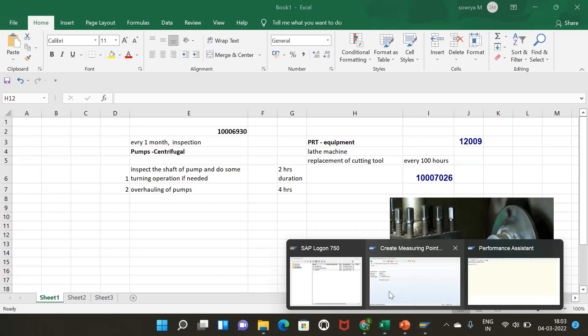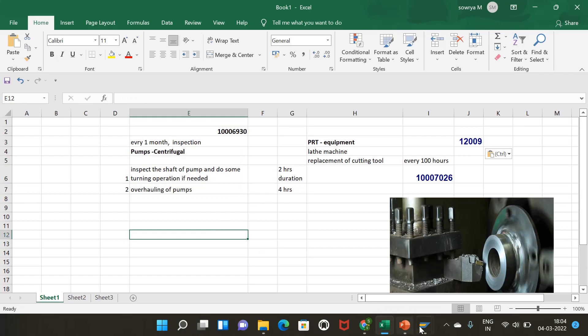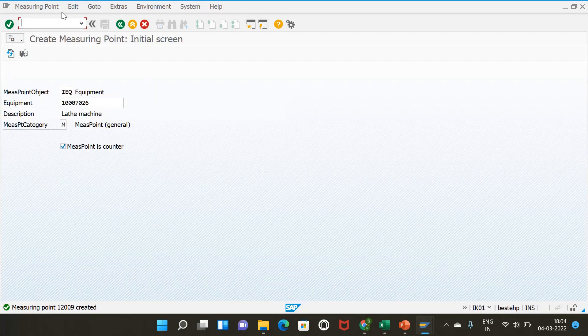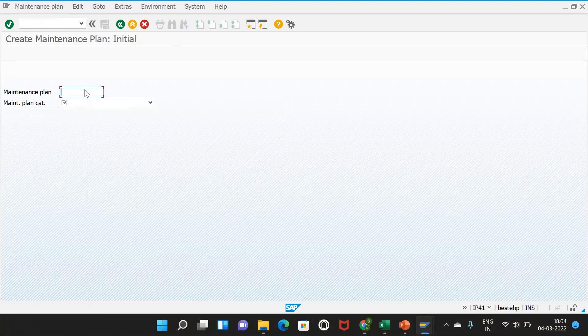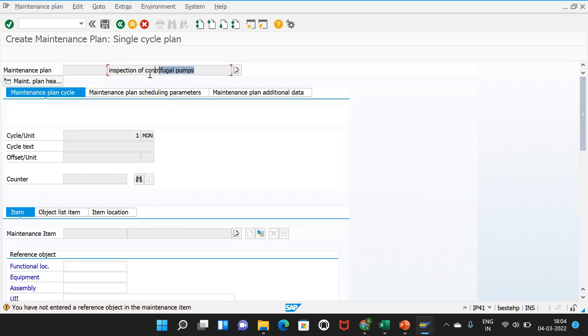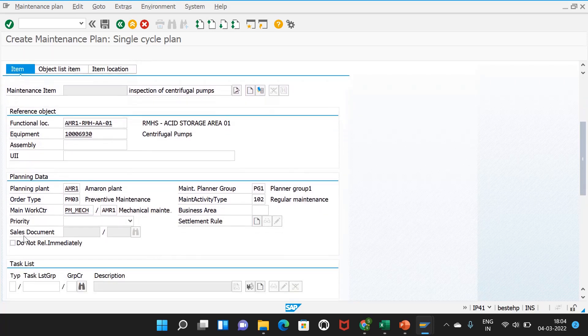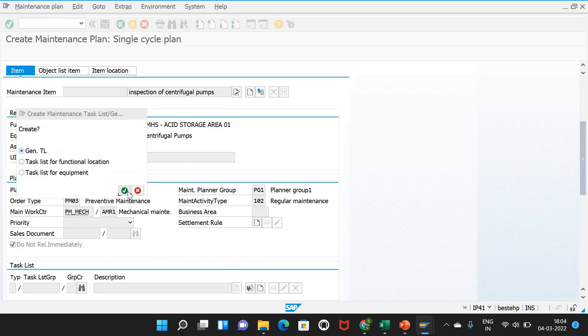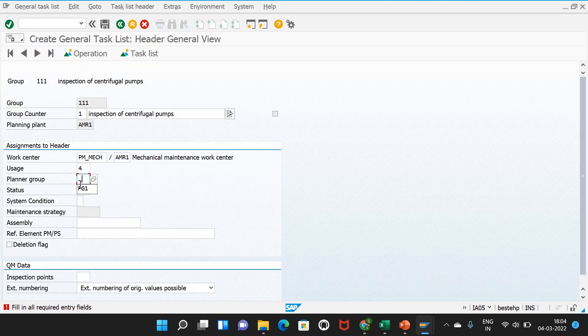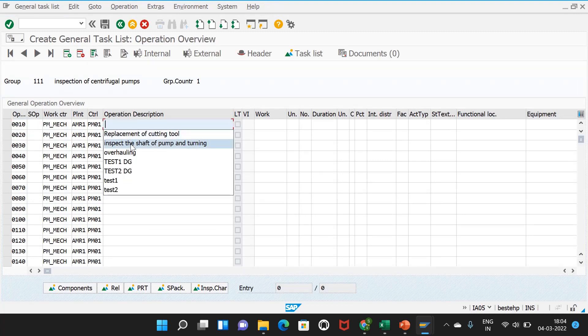Now we create the business processes. We will create a single cycle maintenance plan for the centrifugal pumps in transaction IP41. The call object is maintenance order. Description: inspection of centrifugal pumps every one month. The cycle is one month. The equipment is the centrifugal pump and the order type is PM03. We select do not release immediately. Then we create a general task list for the pumps with usage 4, planner group P01, and system condition not in operation.